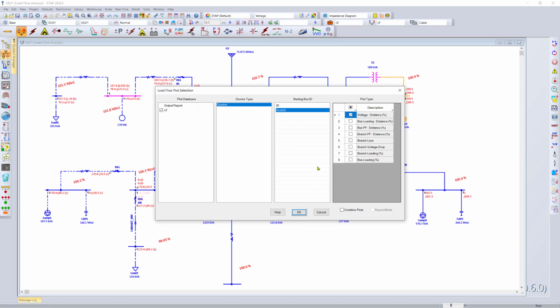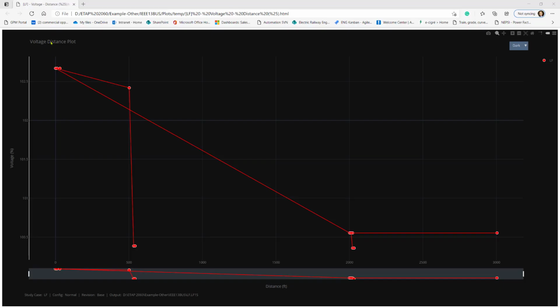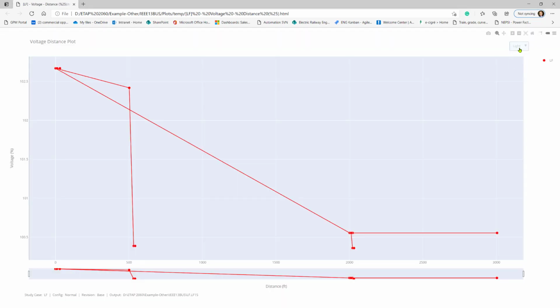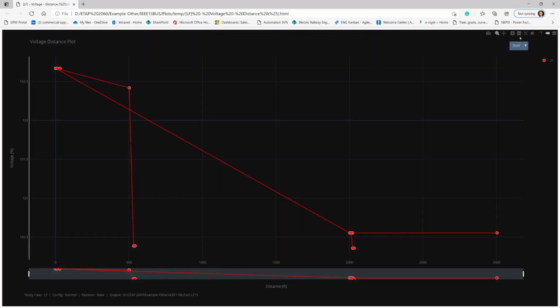Let's go ahead and plot voltage versus distance. What we see is a voltage versus distance plot that gives us our voltage in percentage and the distance in feet. And by hovering on any of these points, you can easily visualize the voltage, the bus ID, as well as the distance from the swing source. And as in a traditional plot analyzer, you can always switch between dark and light modes and interact with the diagram using the controls on the top right corner.